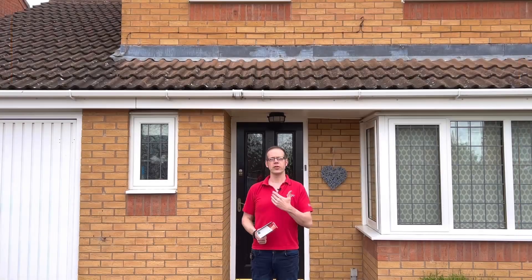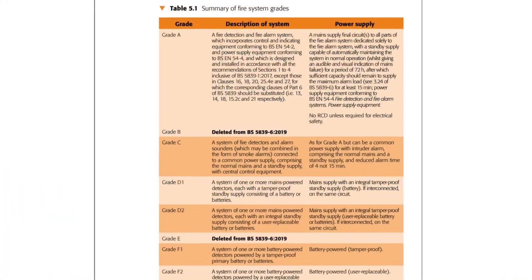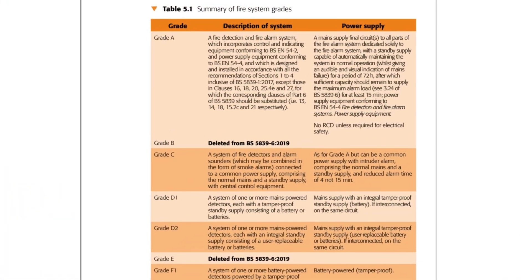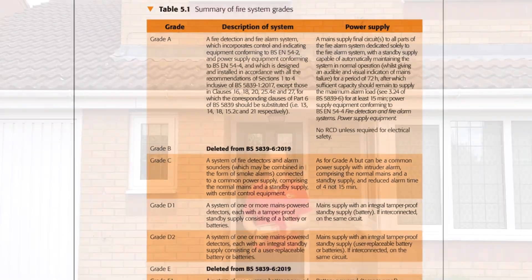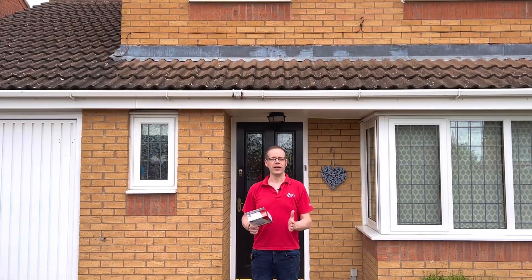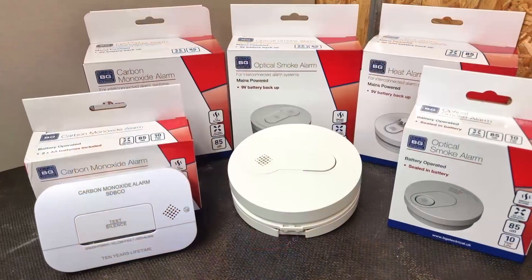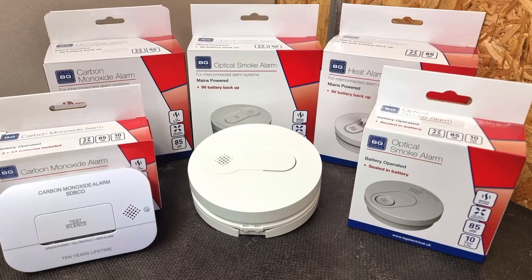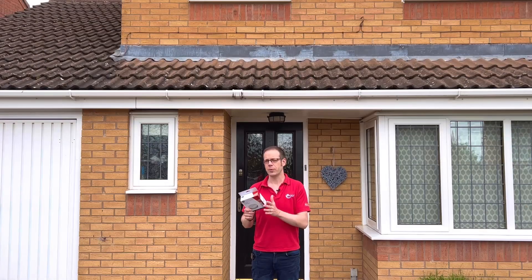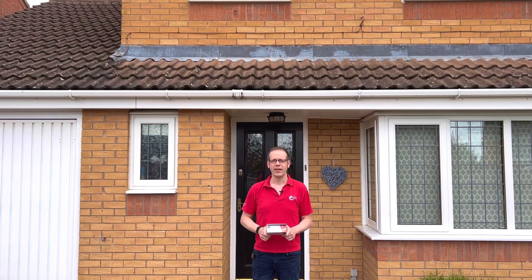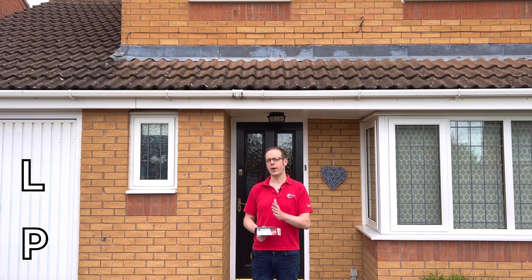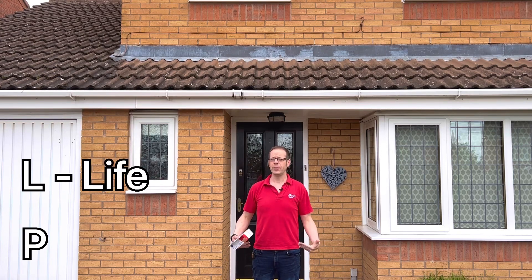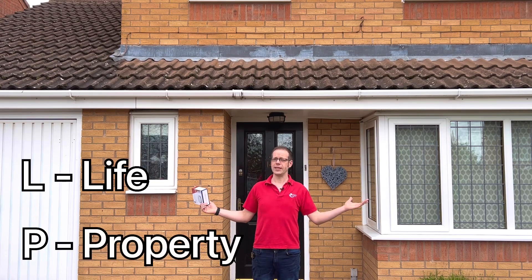We've discussed grades of fire detection in a previous video and now we're looking at categories. What's the difference? Well, a grade in this context is all about the system and the equipment being used, whereas categories are more about what the fire detection system is protecting. The categories break down into two areas with the identifying letters L and P, where L stands for the protection of life and P stands for the protection of property.